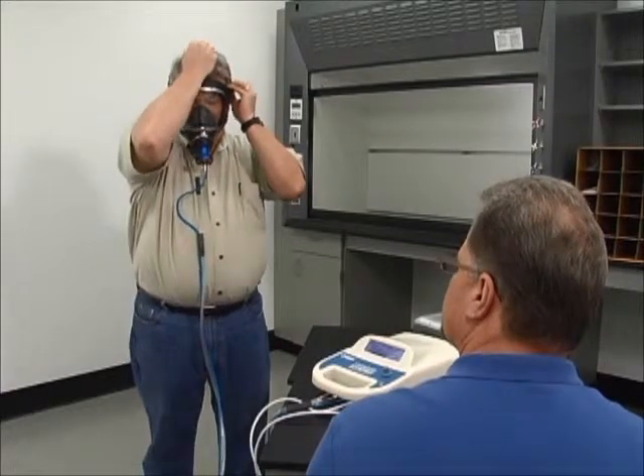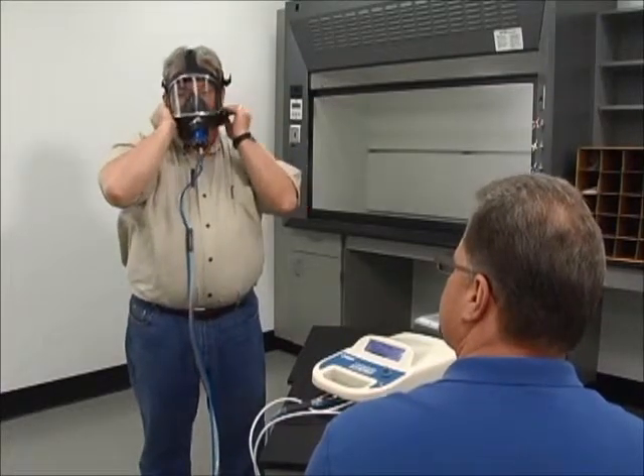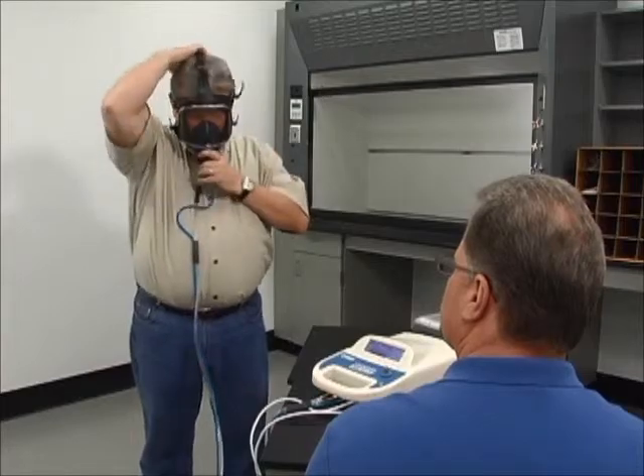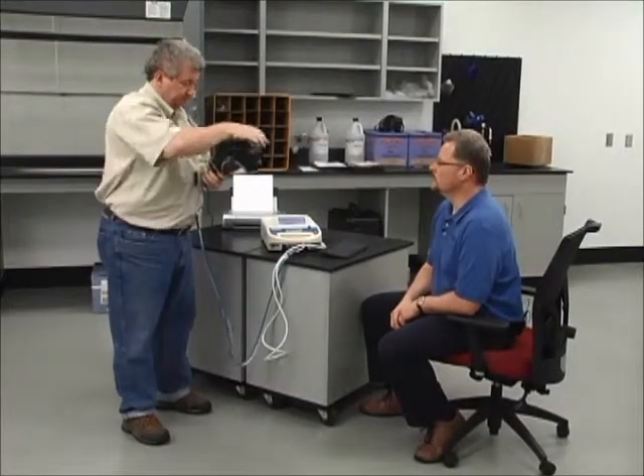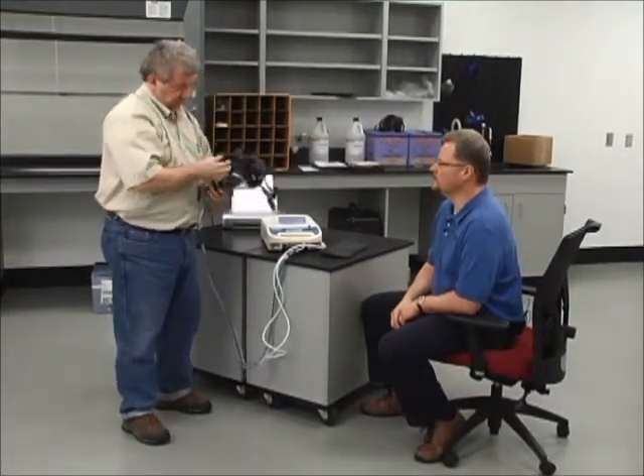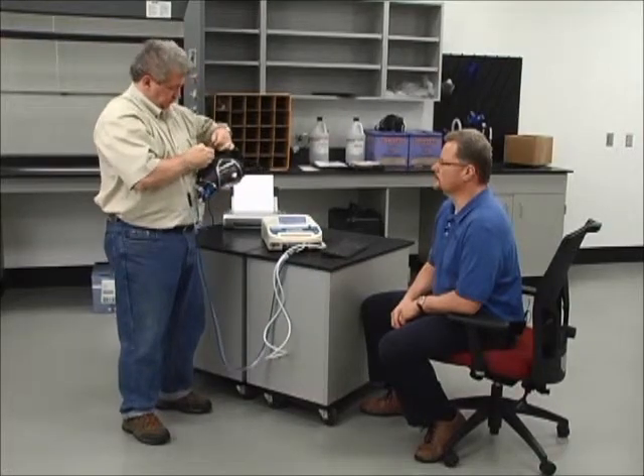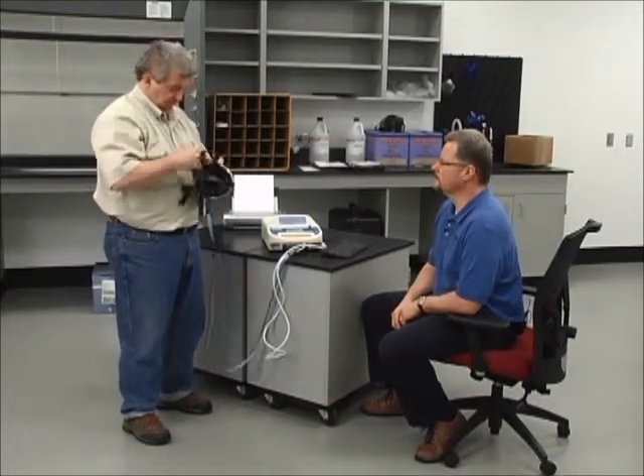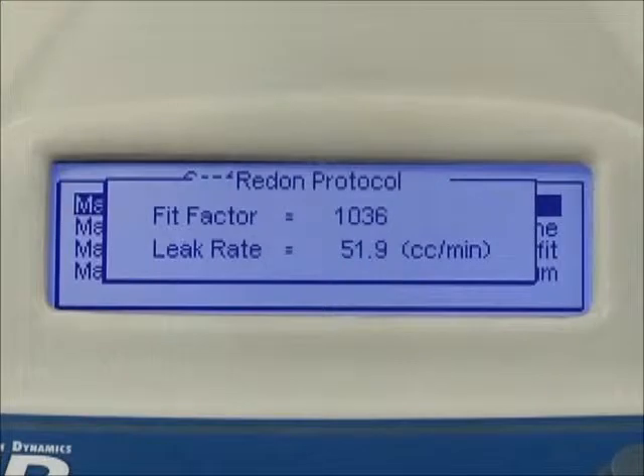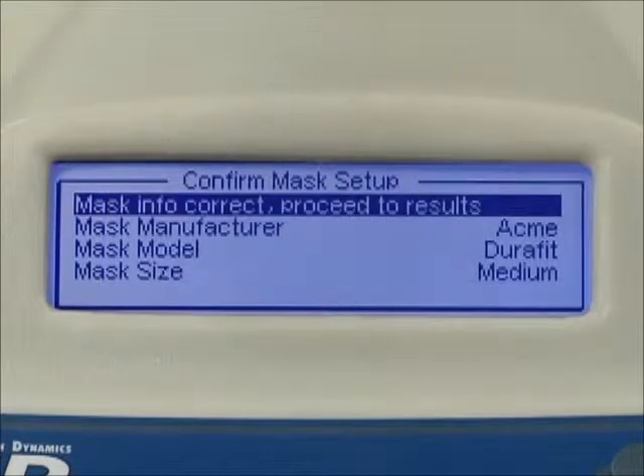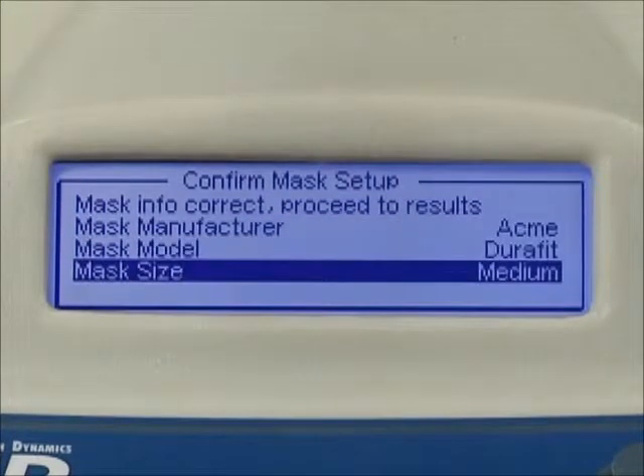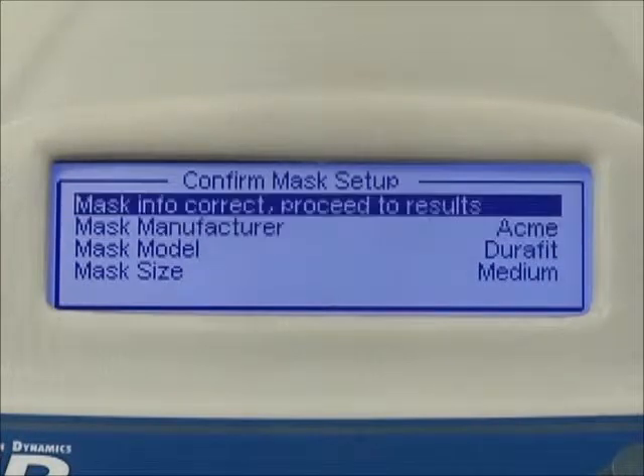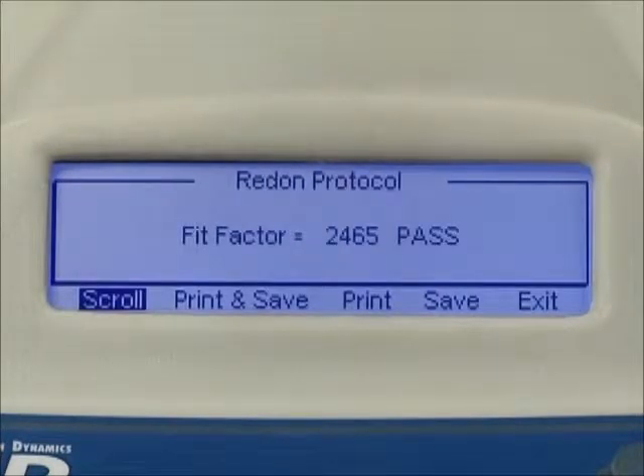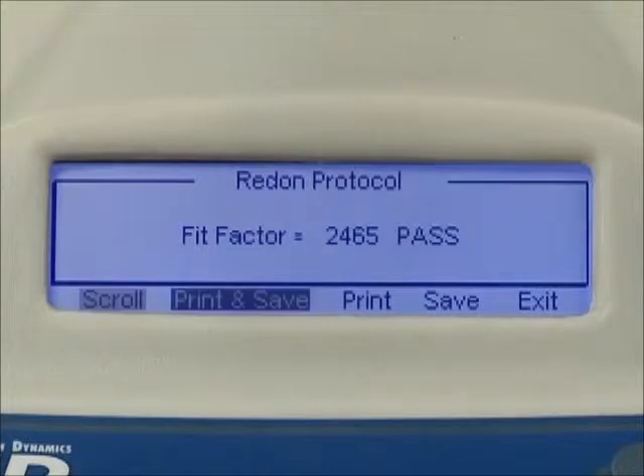Each Redon step is critical in recognizing potential problems in the donning of the respirator. The fit factors produced after each Redon can reveal problems the subject may have when donning and adjusting the respirator. Once you save the final Redon step, verify the mask model and size before saving the test. The Quantifit will display the overall fit factor and the percent of leak rate in the machine's display.